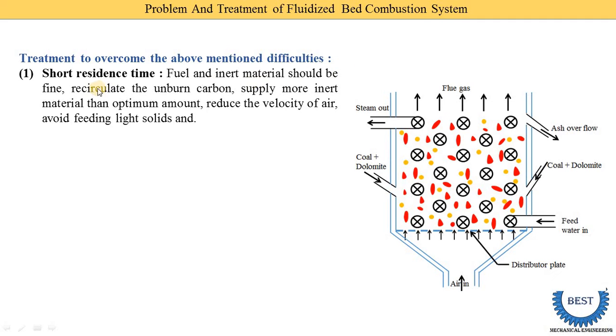Fuel and inert material shall be made finer, meaning their size should be smaller. Recirculate the unburned carbons — if unburned carbon particles remain, we need to arrange a system to recirculate them. Supply more inert material than the optimum amount — there is a fixed ratio for coal and dolomite, but we need to supply more inert materials than the optimum value. Reduce the velocity of air, because if the air velocity is higher, the residence time of the fuel is reduced.